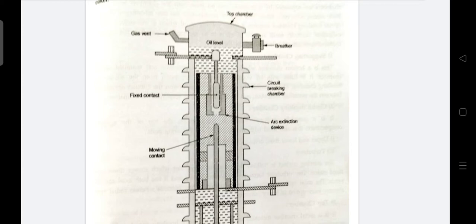It is observed that oil serves two purposes. Firstly, it acts as an arc quenching medium and secondly it insulates live parts from the earth. It is found that only a small percentage, about 10% of oil is used for arc extinction process and major part is used for insulation purpose.